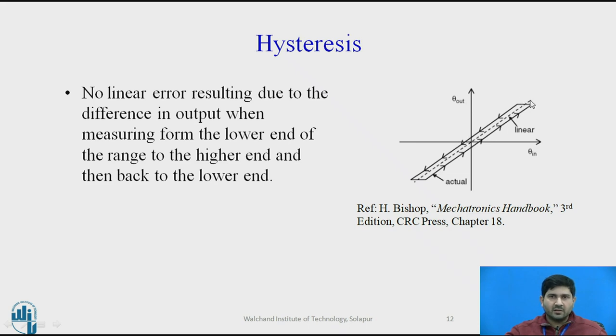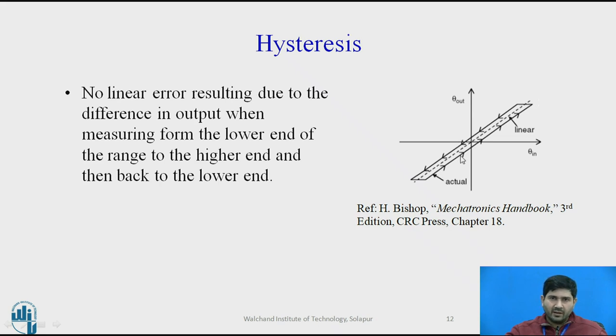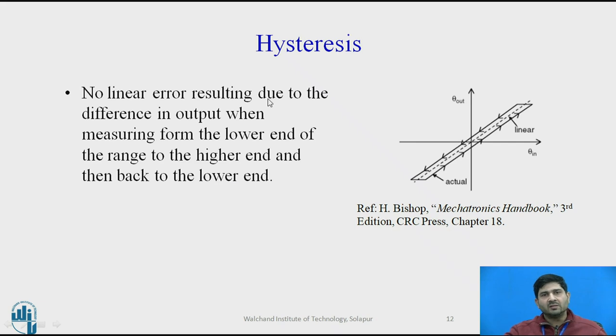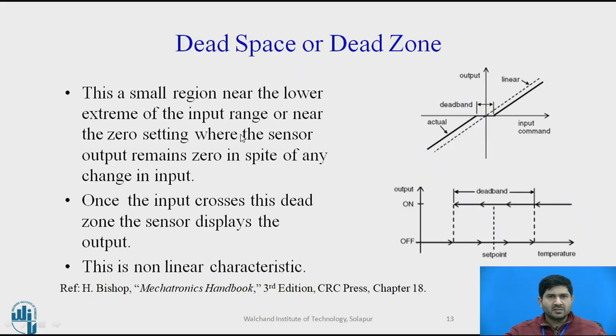Another important characteristic is hysteresis. Measurement is typically bi-directional — as the quantity being measured rises in value and also when it decreases. This measurement is never perfectly constant, so you typically get a band called the hysteresis loop. It is a non-linear error resulting from the difference in output when measuring from the lower end of the range to the higher end and then back to the lower end. Hysteresis is one of the major sources of bias errors in sensors.